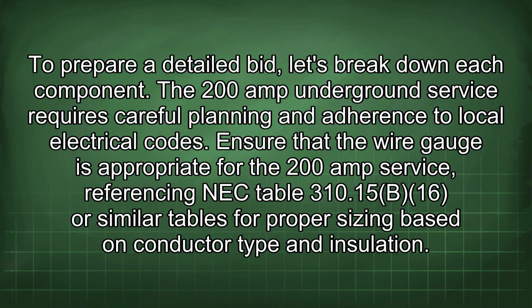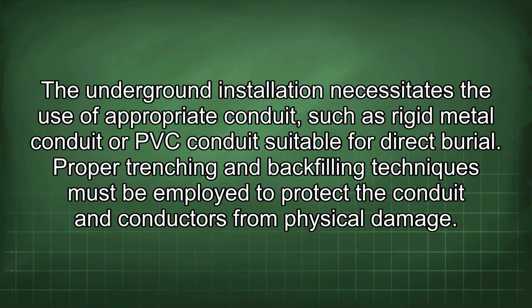The 200 amp underground service requires careful planning and adherence to local electrical codes. Ensure that the wire gauge is appropriate for the 200 amp service, referencing NEC Table 310.15(B)(16) or similar tables for proper sizing based on conductor type and insulation. The underground installation necessitates the use of appropriate conduit such as rigid metal conduit or PVC conduit suitable for direct burial. Proper trenching and backfilling techniques must be employed to protect the conduit and conductors from physical damage.